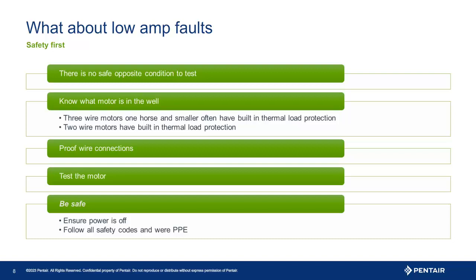Just like a high-amp fault, proof the wire connections and ensure they are tight and secure. Another note about 2-wire connections: the motor wires need to go to the yellow and black. Any other combination will cause the unit to fault. Finally, test the motor as discussed earlier. Be sure to review the data from the motor manufacturer information and always work safe, follow all regulations and wear PPE, personal protective equipment.